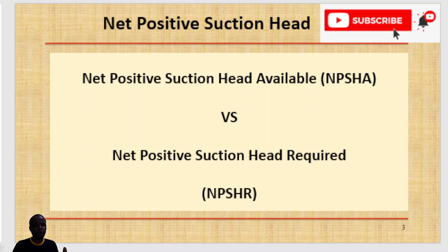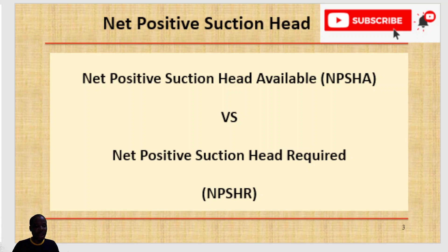We have the NPSHA, which is the net positive suction head available, and NPSHr, which is the net positive suction head required. We'll be looking at both in this session. Pump manufacturers determine by tests the NPSHr at various capacities for a particular pump. Conversely, the NPSHA is the net positive suction head available in the system.